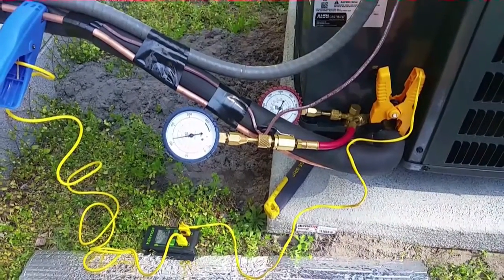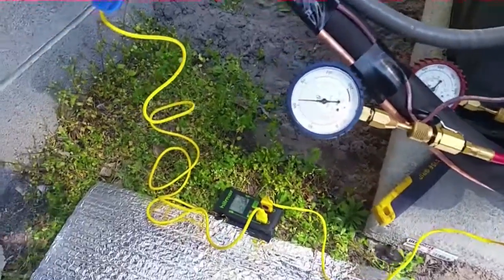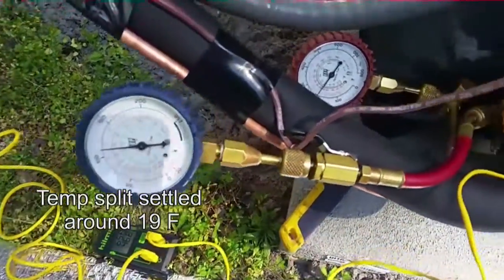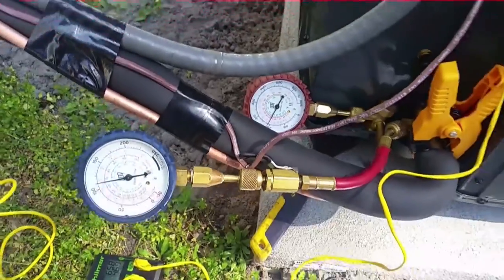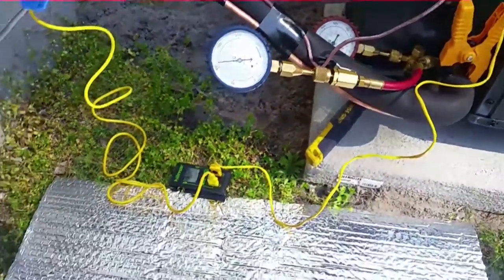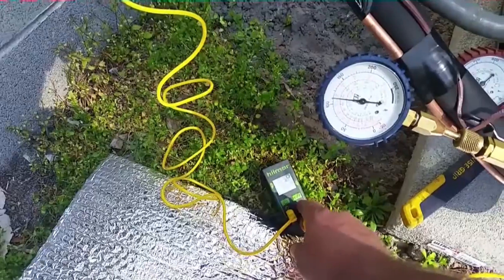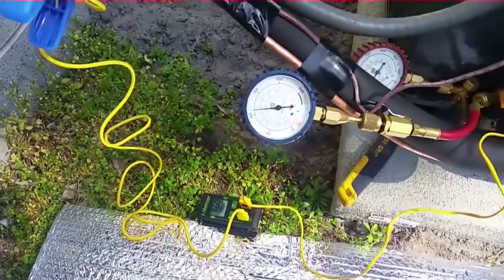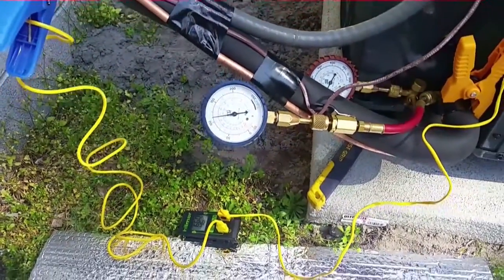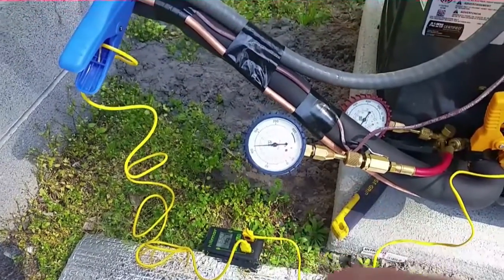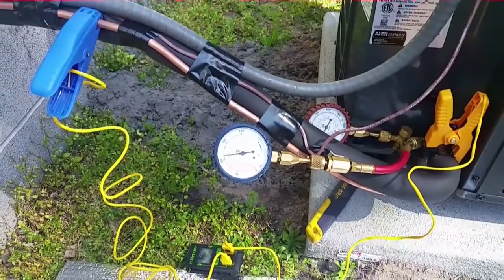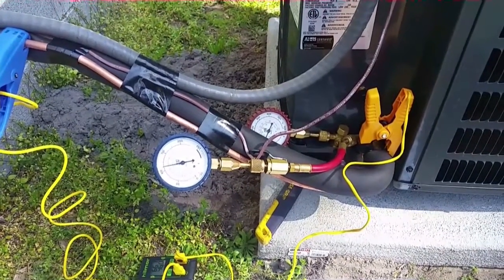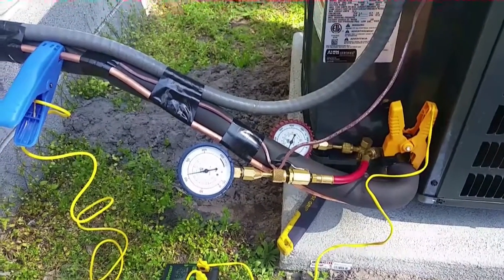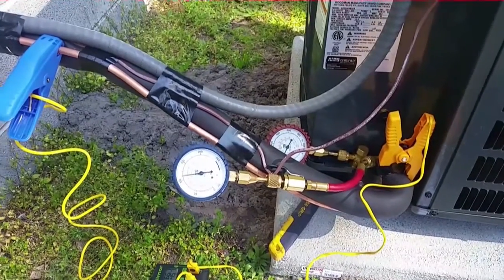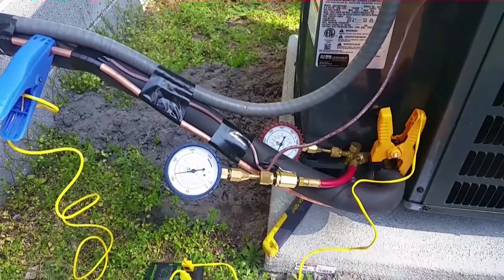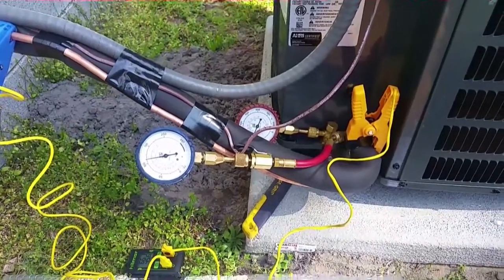As you guys can see, we had about an 18-degree temperature difference. We are running at around 110 pounds on the suction side, getting nice and cool inside. Right around 220 on the high side. Temperature is 46, fluctuating between about 48 and 46 as far as I could tell, and about 66. So we have around 8 degrees of subcooling and between 10, 12 degrees of superheat. So everything looks pretty good there. We had our 18-degree differential inside, which indicates that we have probably around 45 to 50% relative humidity inside. So everything's looking good.